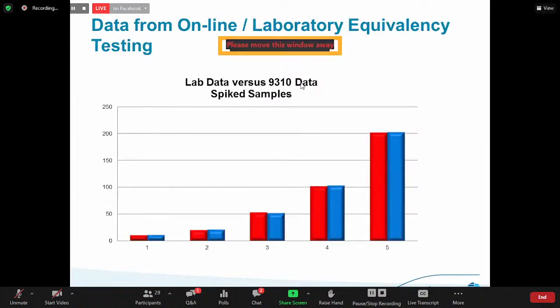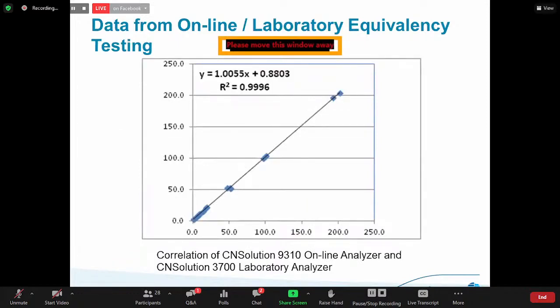And some of the lab versus 9310 data, because this is one of the benefits of the OI Analytical approach: we use the very same technology in both locations. There would not have to be any adjustments or compensations for different types of techniques. It is the same technique that's used in both places. It was interesting to make sure that our lab data versus our 9310 data with representative spike samples does indeed match. And they do if the instrumentation is set up and calibrated the way it should be. Again, this is correlation from the laboratory data, which you see is very, very good.